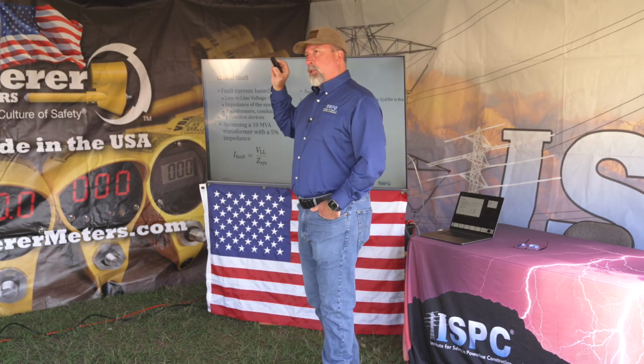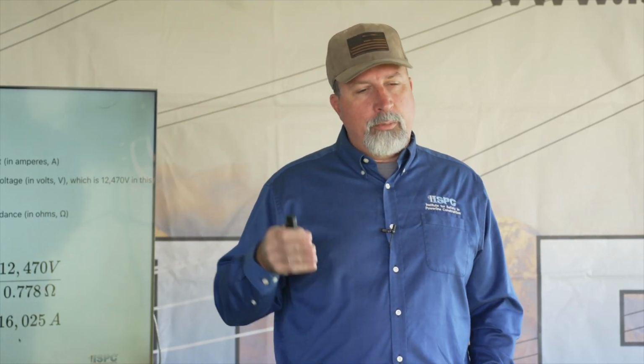A 10-inch standoff post insulator, we assume, we're not 100% sure, but we assume just from examining the after effects, had a hairline crack in it. And in that instant that I was sitting there, that voltage tracked to ground. And we had a phase to ground fault. I'm going to show you the calculation for a phase to ground fault here in a minute, similar to this phase to phase fault.